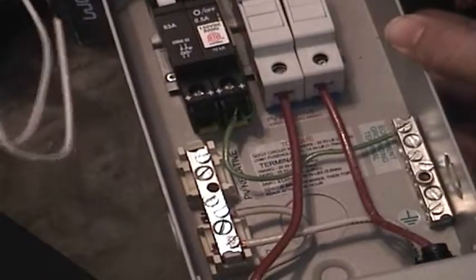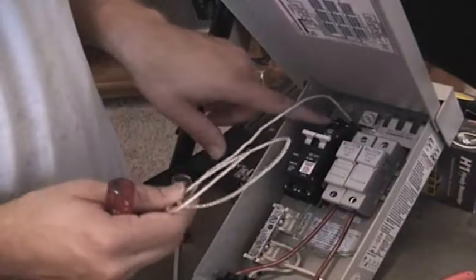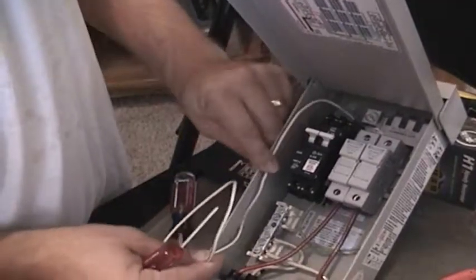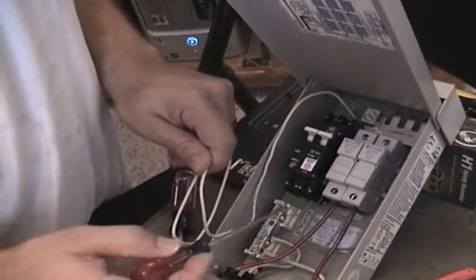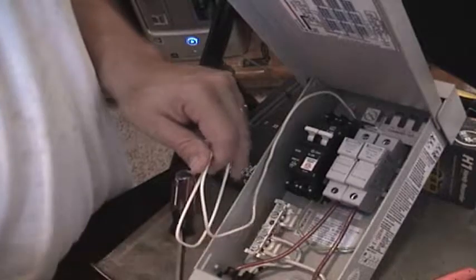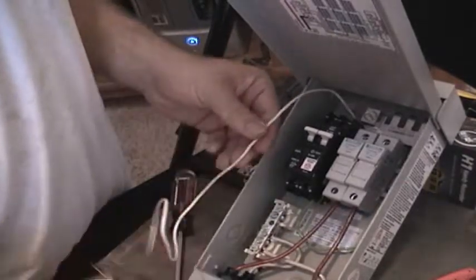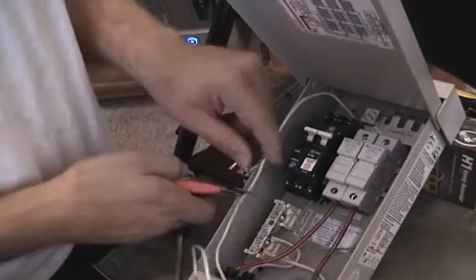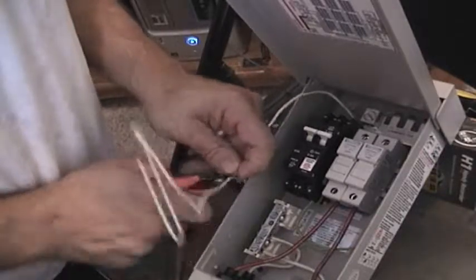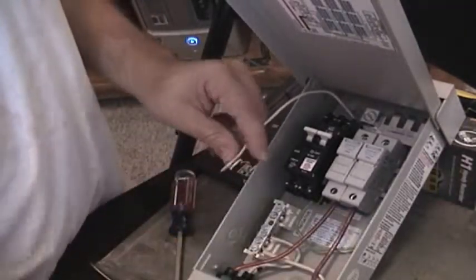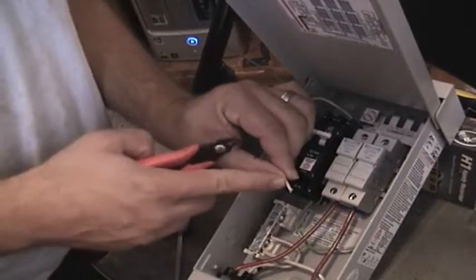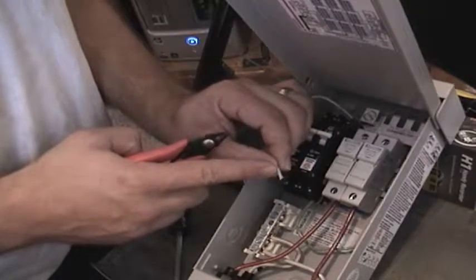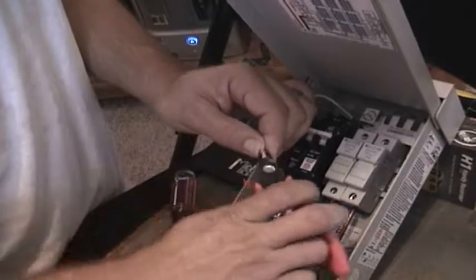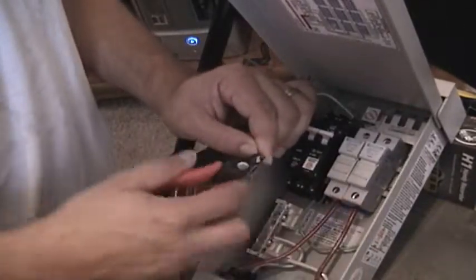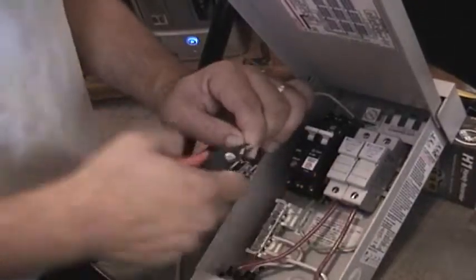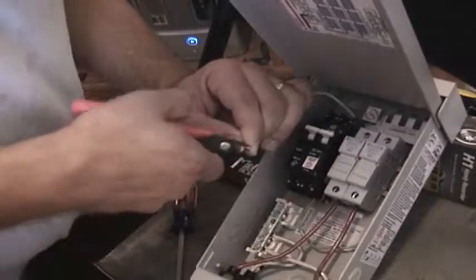Okay, now let's do the white wire. Now let's take the white wire coming from the top of the GFP device, and we're going to run it down to the PV negative bus bar, and we're going to mount it in this top mounting hole. We only need about 6 or 7 inches to do that, so let's get our wire clippers and cut off the excess wire. And again, we need to strip about 1/2 inch of the skin off from the end of the white wire. We can do that with our wire clippers. Again, be careful, don't cut into the conductor. Just kind of play with it until it comes off.